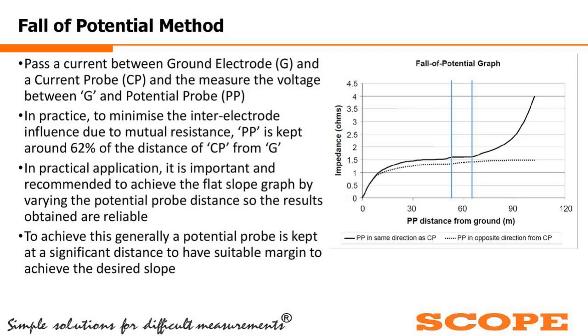So the potential probe distance should be around 62% of the distance from the current probe to the injection point G. This is the reason it is recommended to measure with a long distance cable, which was also explained in the previous slide. To achieve this, generally a potential probe is kept at a significant distance to have a suitable margin to achieve the desired slope. So we are trying to achieve our measurement in this flat or horizontal area in between the two vertical blue lines, which comes from the fall of potential graph.